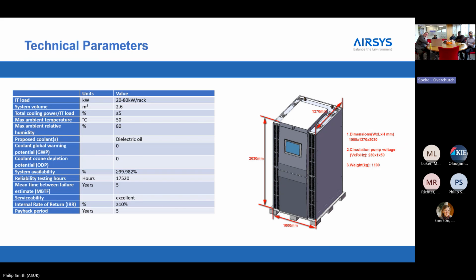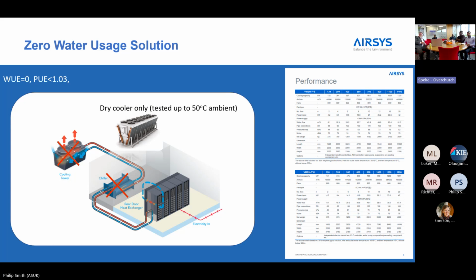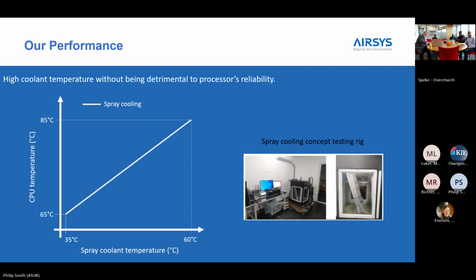What you're doing then is you are linking that dielectric fluid through one half of a brazed plate heat exchanger. On the other half, you've got, again, water pipework going out to a dry cooler. So you are directly rejecting the heat from the CPU into the dielectric and then cross into condenser water, taken away. The dielectric's running at anything up to 60 degrees C, which is very efficient, which means that your heat rejection plant is quite small compared to the load that you're actually rejecting. But more importantly, you've got potential to recover heat from that before you reject it outside.